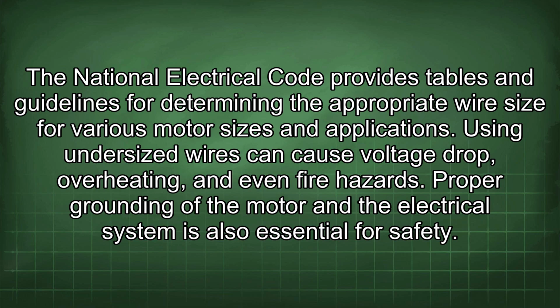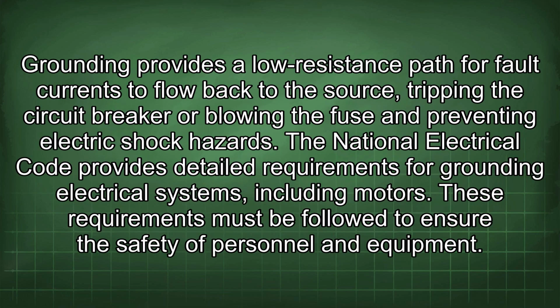Proper grounding of the motor and the electrical system is also essential for safety. Grounding provides a low resistance path for fault currents to flow back to the source, tripping the circuit breaker or blowing the fuse and preventing electric shock hazards. The National Electrical Code provides detailed requirements for grounding electrical systems, including motors. These requirements must be followed to ensure the safety of personnel and equipment.